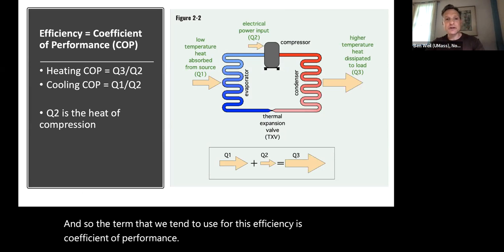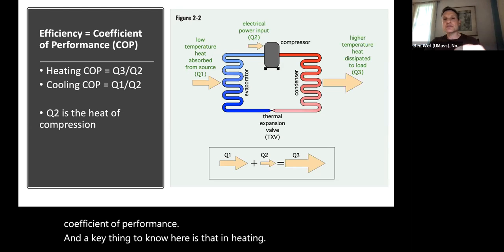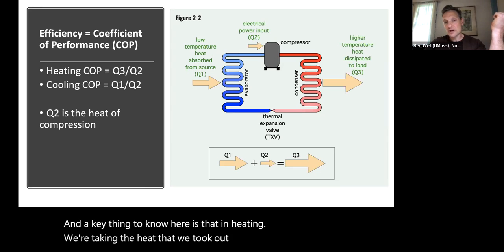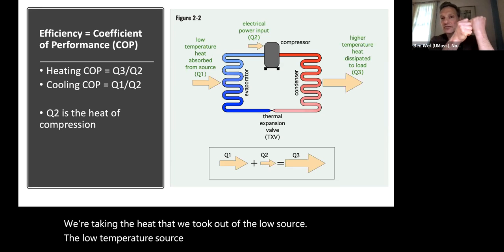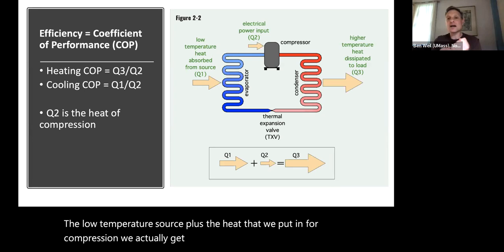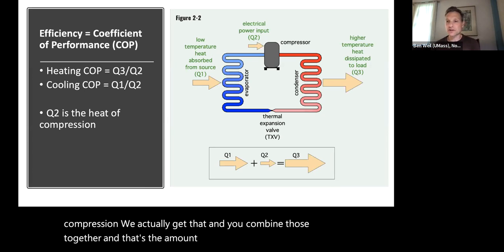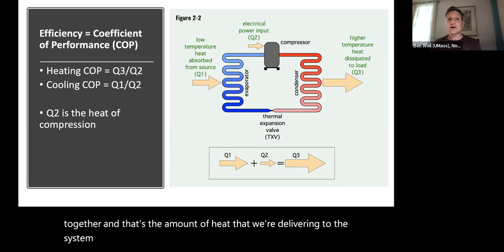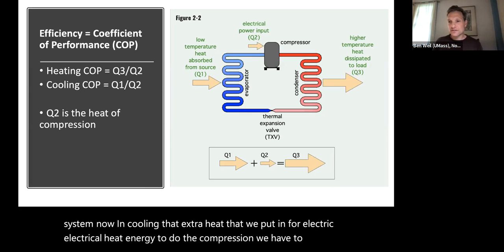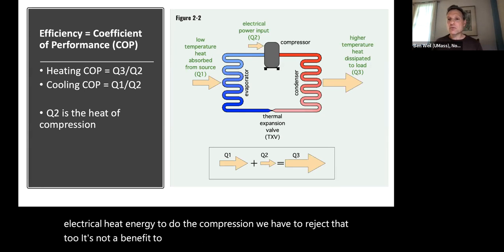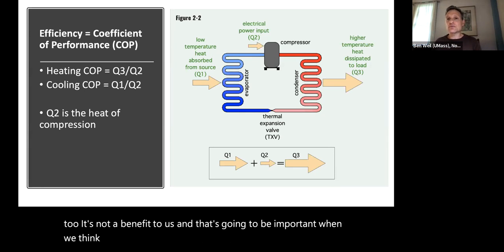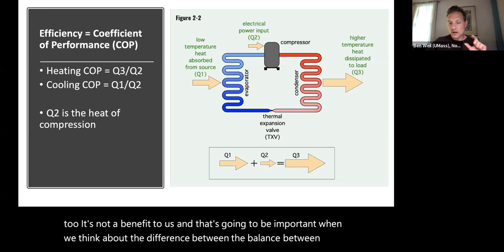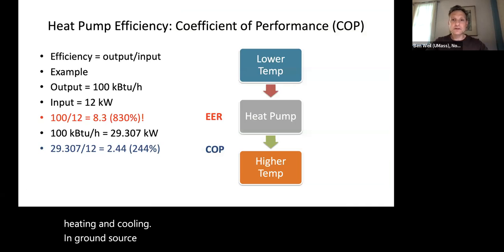And a key thing to know here is that in heating, we're taking the heat that we took out of the low temperature source, plus the heat that we put in for compression. We actually get that. And you combine those together, and that's the amount of heat that we're delivering to the system. Now, in cooling, that extra heat that we put in for electrical heat energy to do the compression, we have to reject that too. It's not a benefit to us. And that's going to be important when we think about the balance between heating and cooling in ground source heat pumps in particular.